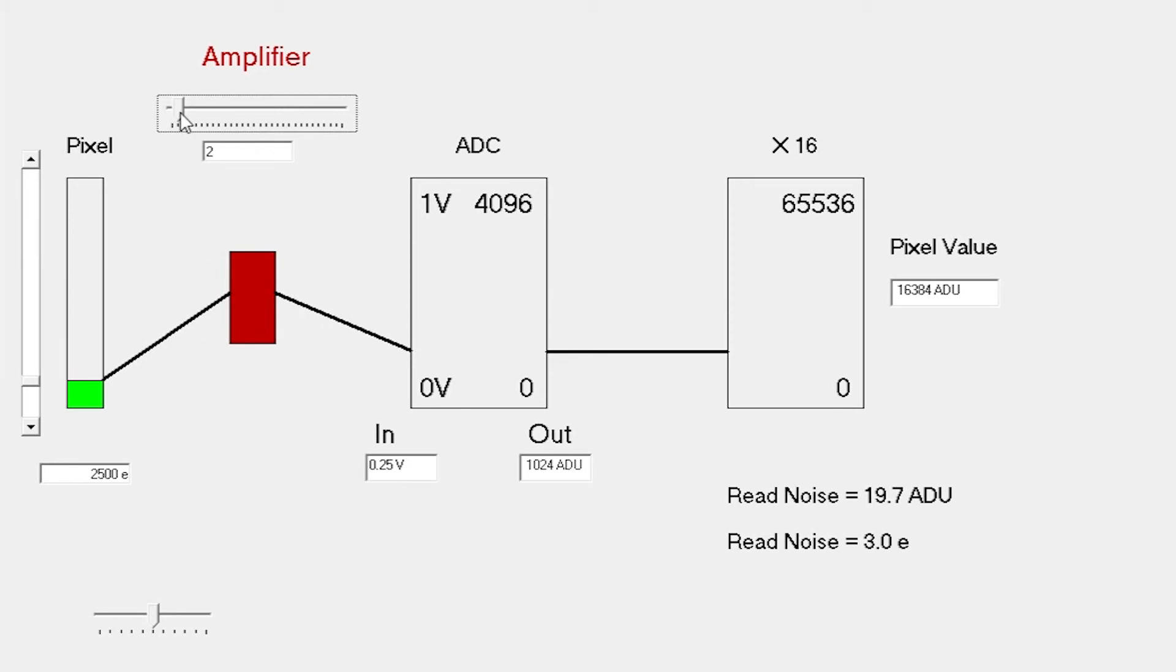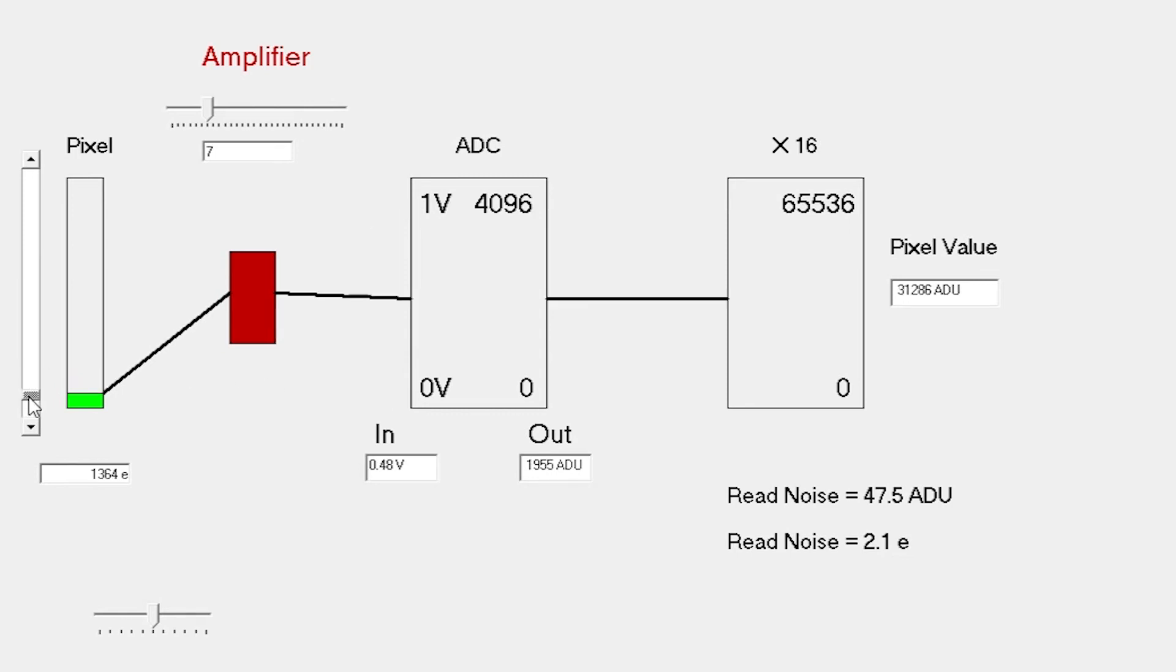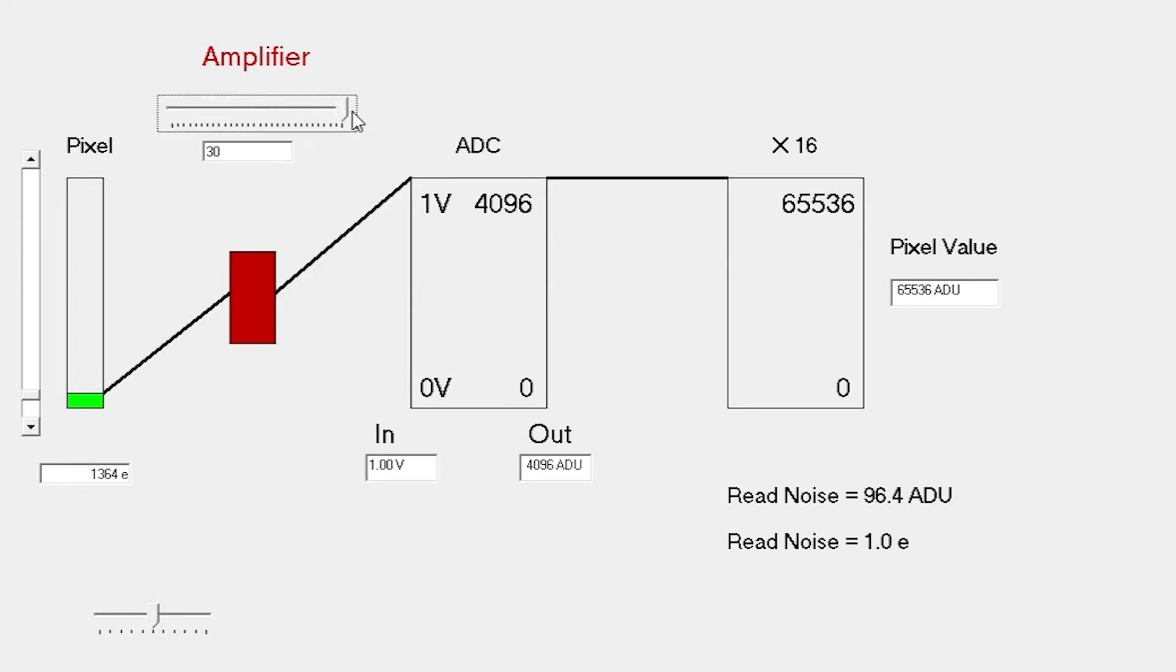As we increase the gain, we're getting smaller and smaller values for read noise. However, we do have to be careful that the amount of signal that we can actually measure is going down. We're really concentrating on the smaller end of the pixel full well. We can increase the gain factor all the way up to a gain of around 30. That gives us a read noise right down around 1 electron, which is far better than any CCD.